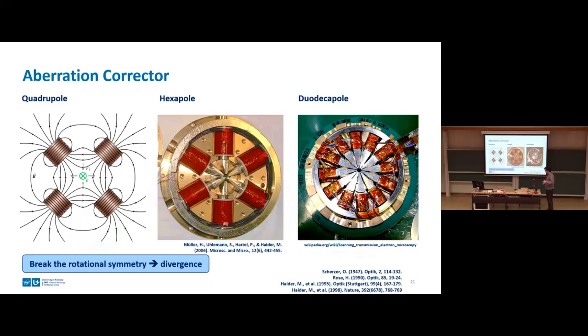A good animation of that is in this beautiful video from Veritasium, which I recommend. The electrons will pass through the hexapole. They will be shaped in this kind of triangular way, and it will have effectively a small divergence applied to this propagating wavefront. Then we have a 30 degrees rotated hexapole again, and then we're back to our aberration-free probe, and it continues along the optical axis of the microscope. But going back to where we started, what these aberration correctors effectively also introduce is more multi-dimensionality to the microscope.